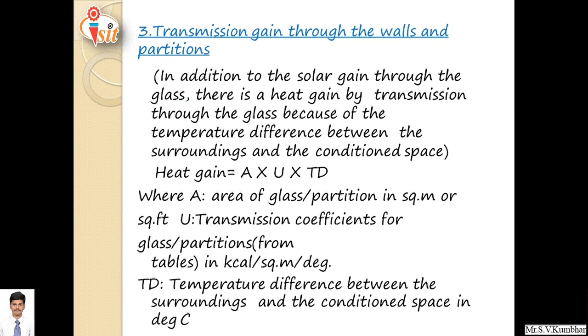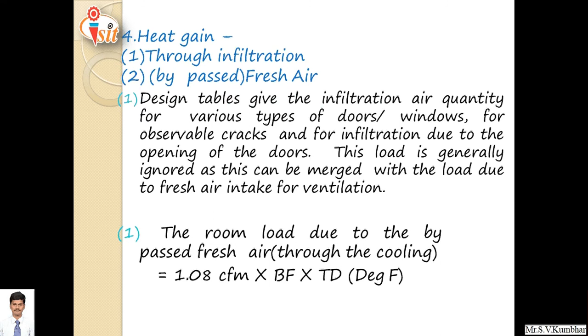Heat gain through infiltration. Whenever doors and windows are opened and closed, this heat gain takes place through infiltration. Second, bypassed fresh air. Here the design table gives the infiltration air quantity for various types of doors and windows. For that purpose, we have to observe cracks and infiltration due to the opening of doors. The room load due to the bypassed fresh air is calculated by 1.08 into CFM into BF into TD.